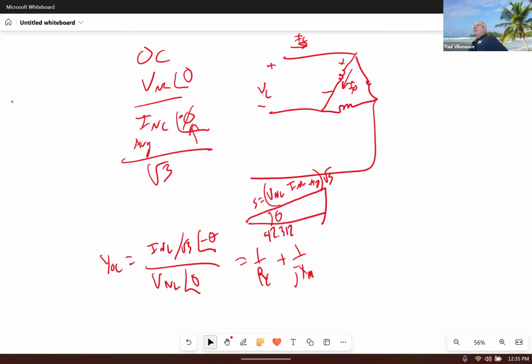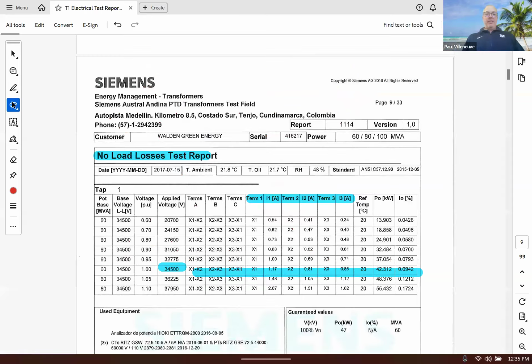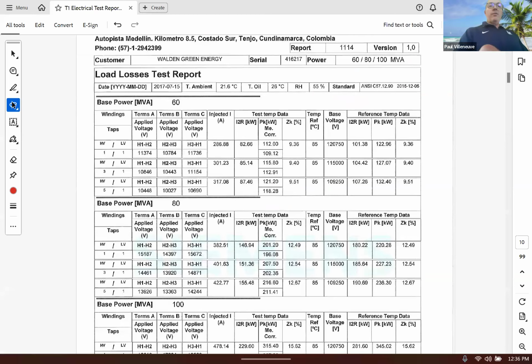That's the no load test. Now I've got 2 out of the 4. Now I'm going to go to my load loss test. So over here, I'm going to use my base transformer rating of 60 MVA, and I'm going to use my nominal tap position, which is right here. So that tells me the voltages, or the 3 voltages that I have. I also know what the current is, and I'm going to go ahead and do my total power that is corrected. Not the measured, but the corrected power, which is temperature corrected to 20 degrees C.